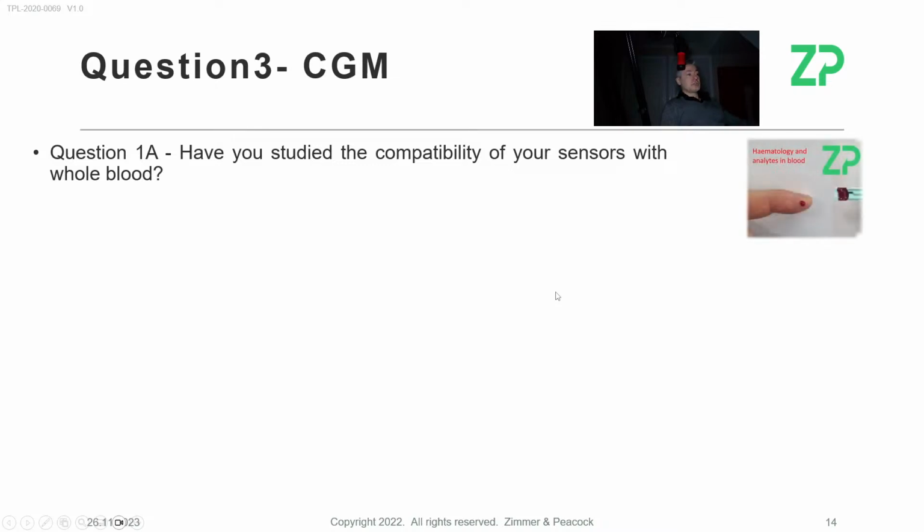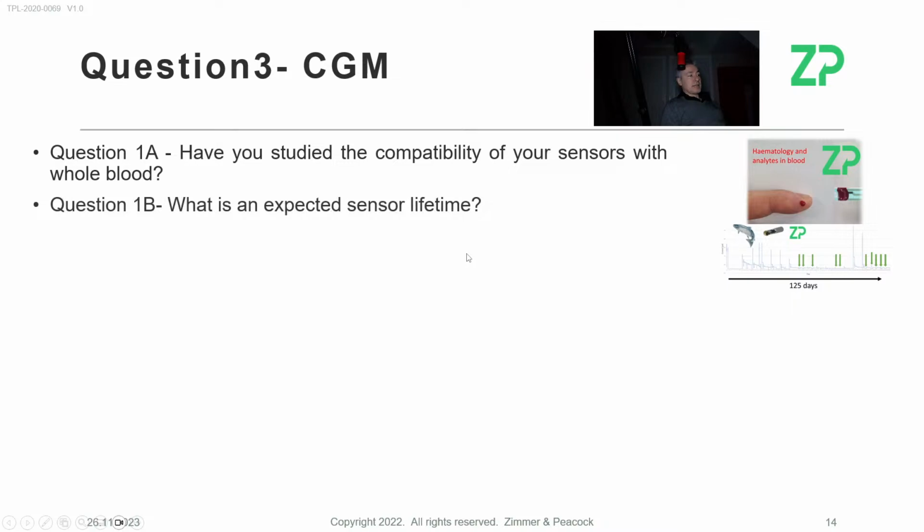Have you studied the compatibility of your sensors with whole blood? The answer is we have, but we've done it with paid clients, and some of that data will be owned by those clients, and we won't necessarily discuss it. Questions like, what's the expected sensor lifetime? If it was a glucose sensor, we've had glucose sensors running out of lab for 9 months continuously.